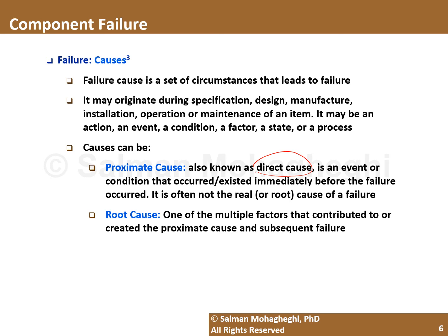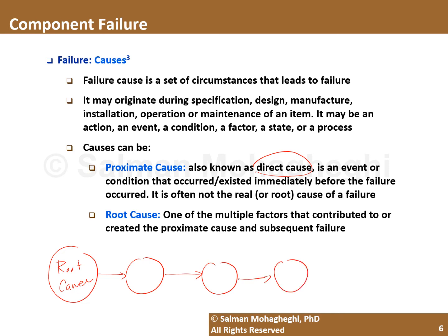So typically, the way it works is that you have the root cause, and then this root cause will lead to certain events or certain conditions through a chain of events, and eventually it gets to the proximate cause, which then leads to the failure. For example, imagine in a power system a short circuit happens between two overhead lines, for example, a line-to-line short circuit. This short circuit is going to be a failure.